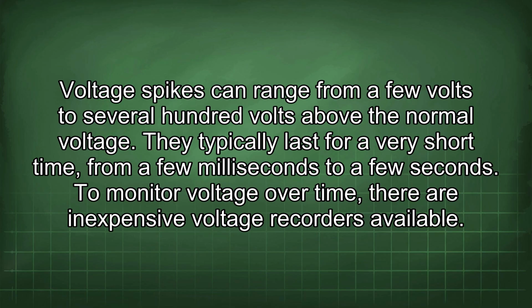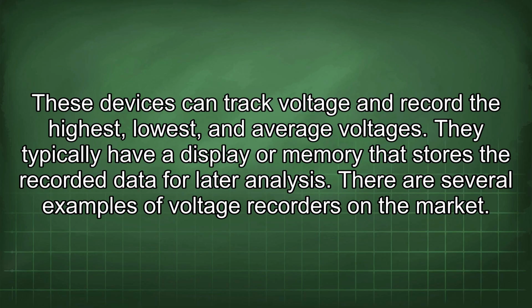Voltage spikes can range from a few volts to several hundred volts above the normal voltage. They typically last for a very short time, from a few milliseconds to a few seconds. To monitor voltage over time, there are inexpensive voltage recorders available. These devices can track voltage and record the highest, lowest, and average voltages. They typically have a display or memory that stores the recorded data for later analysis.